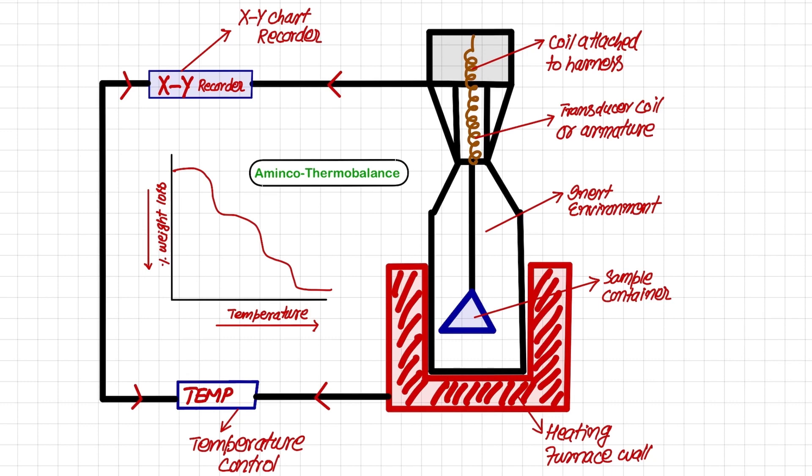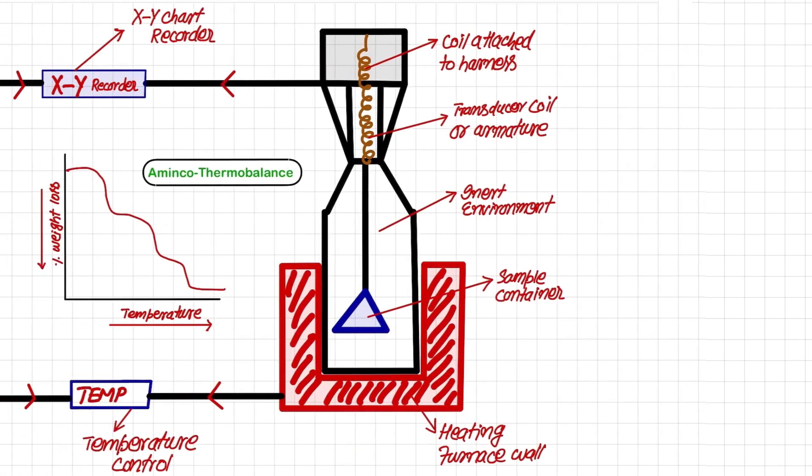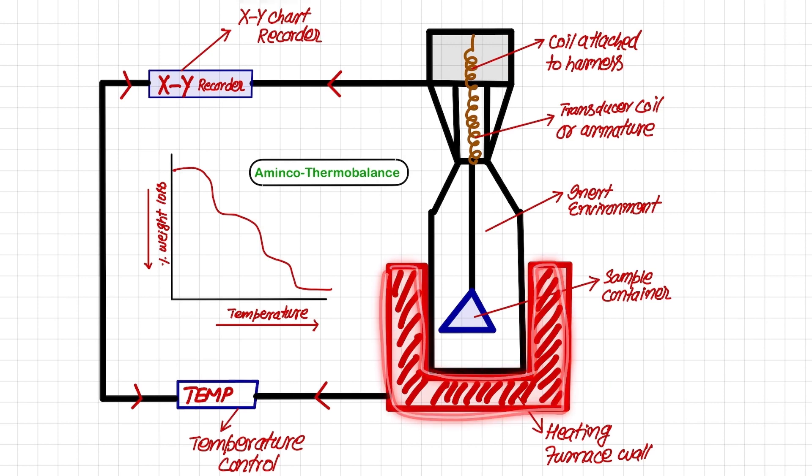These two types of information are then compiled in the form of a graph, and this graph is called a thermogram. As the heating furnace starts heating the sample, there is normally a reduction in weight. Due to the weight reduction, the spring moves upwards and when it moves upwards, a corresponding current is produced. That current is fed to the XY chart recorder and similarly at that instant, the information at that weight change is provided to the XY chart recorder through this temperature control, and then a corresponding thermogram is produced.